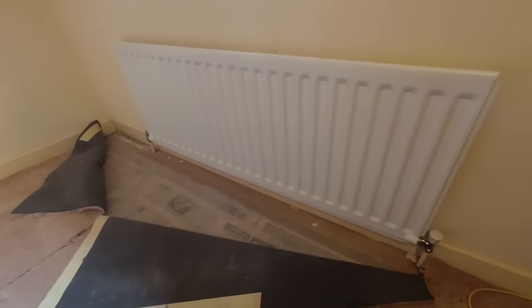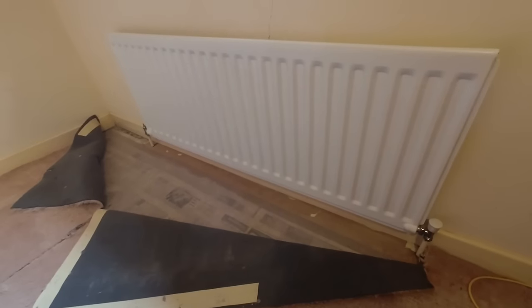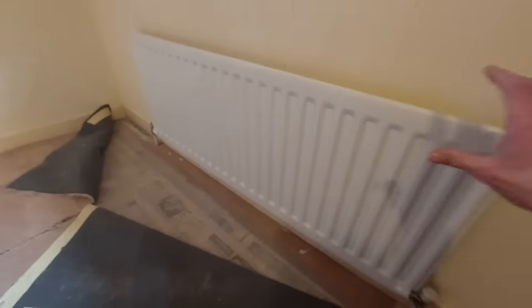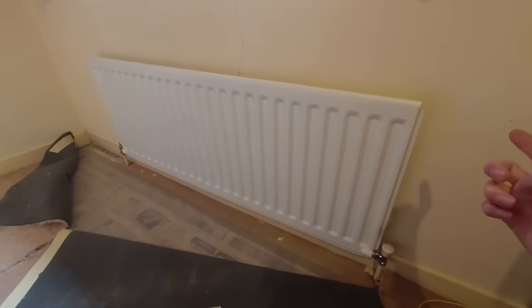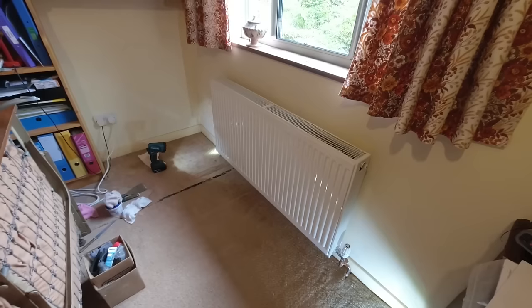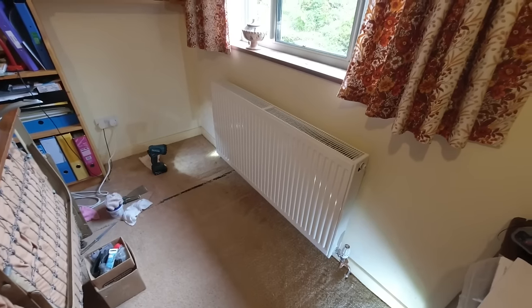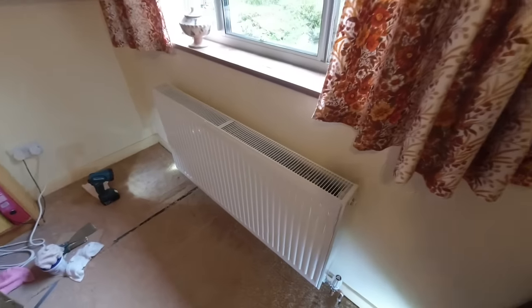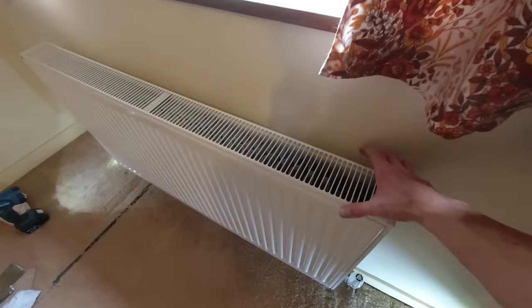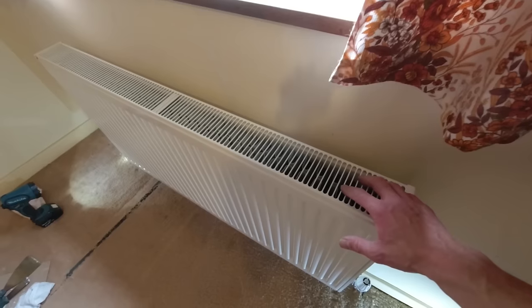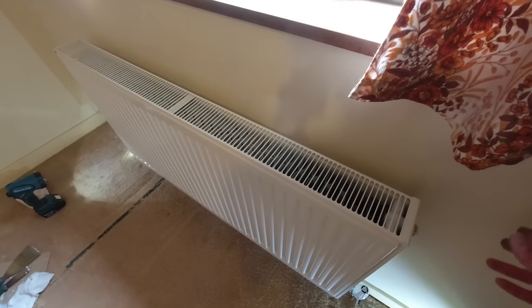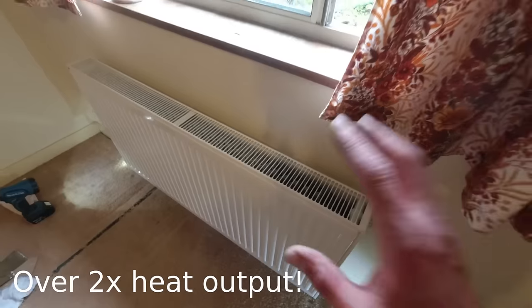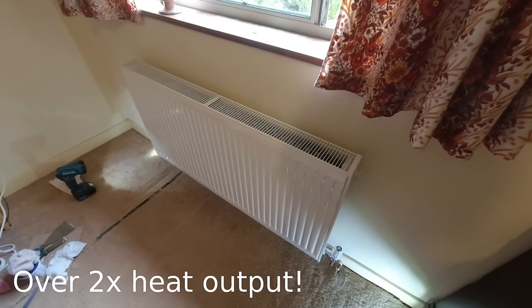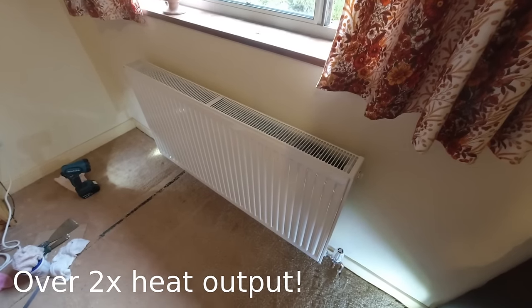And this is one of the bedrooms, and this is a single panel radiator. It's undersized for the room, so we're going to replace it with a much bigger double panel radiator. There we go, new radiator is fitted. This radiator is not much physically bigger, but it's much wider, and it's got a double set of convector fins, where the old radiator didn't have any fins whatsoever, so this will have a much greater output, which will let us run at a nice low flow temperature.